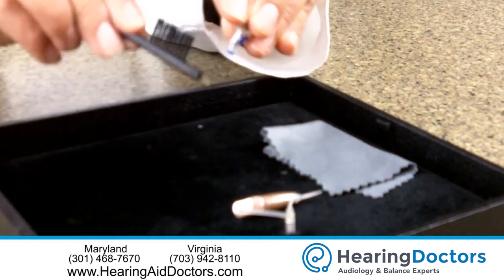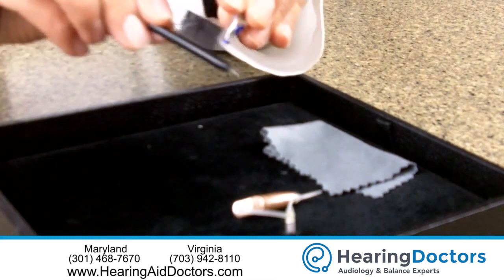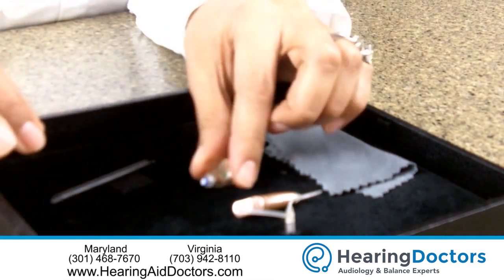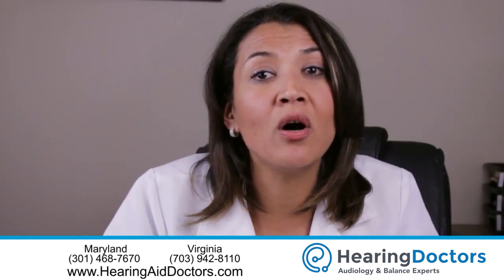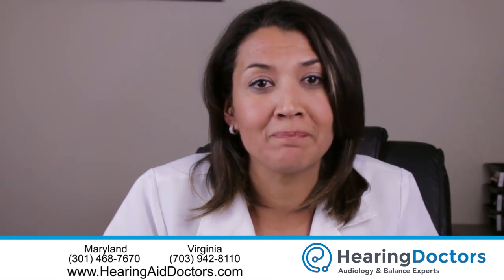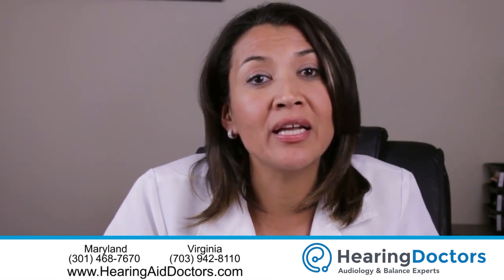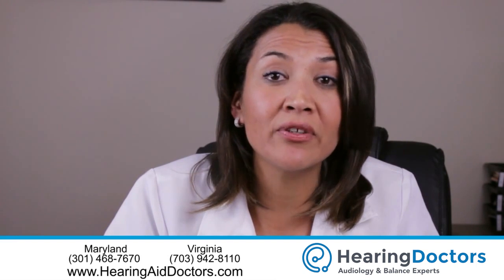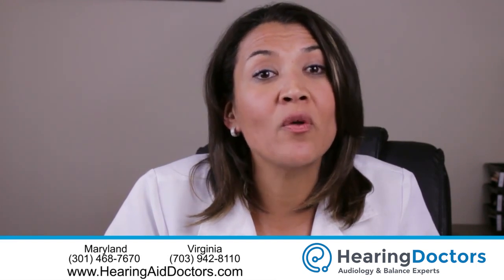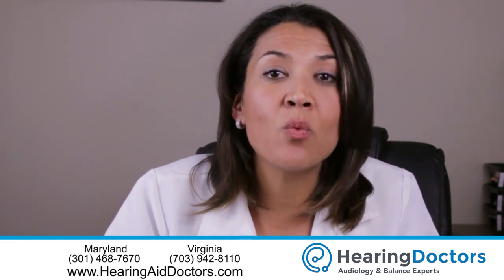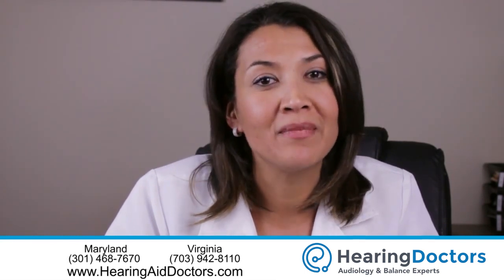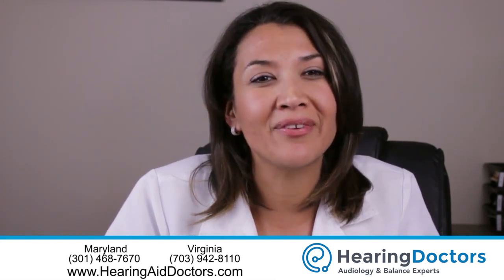It's best to hold the hearing aid's receiver or speaker upside down so that gravity can assist you in removing all the debris that's accumulated. If you have a wax guard in place protecting the receiver, you would then be brushing over the wax guard. Never use water, solvents, cleaning fluids, or oil to clean your instrument. And remember to clean your hearing aids every day.